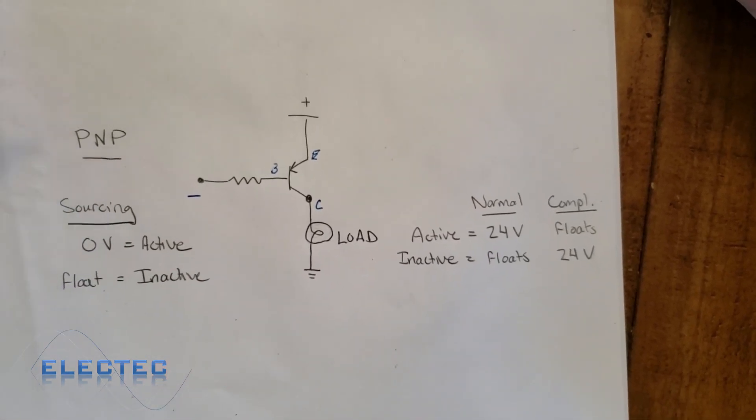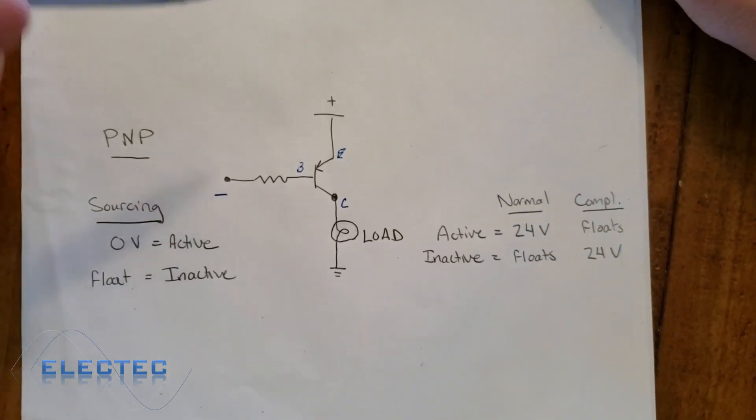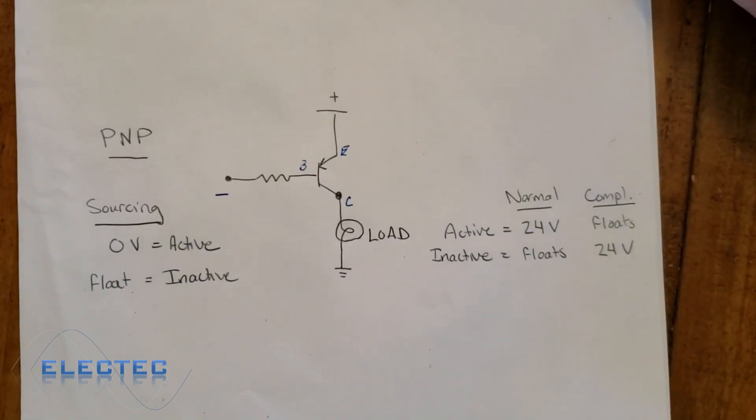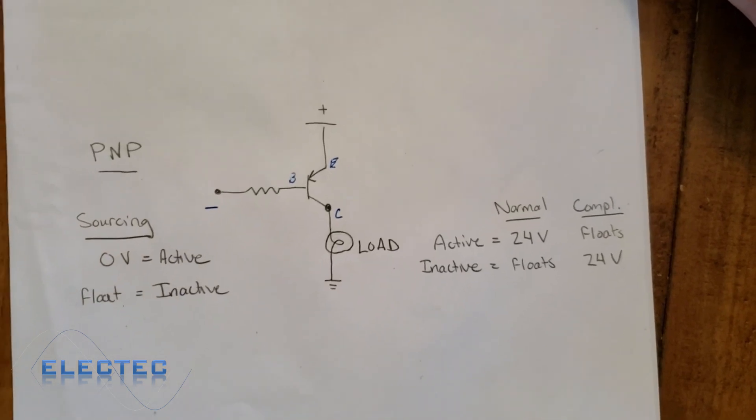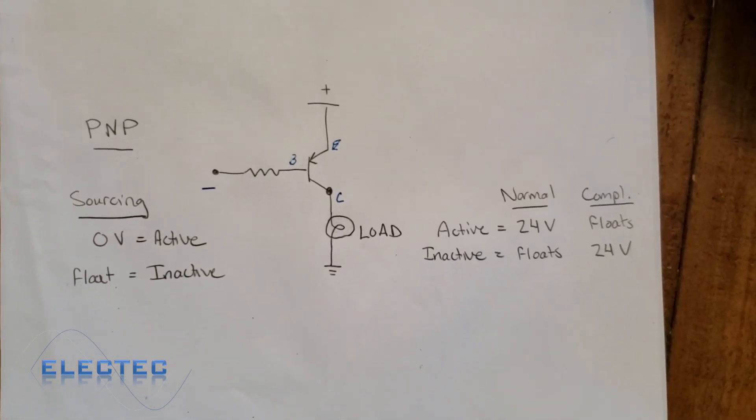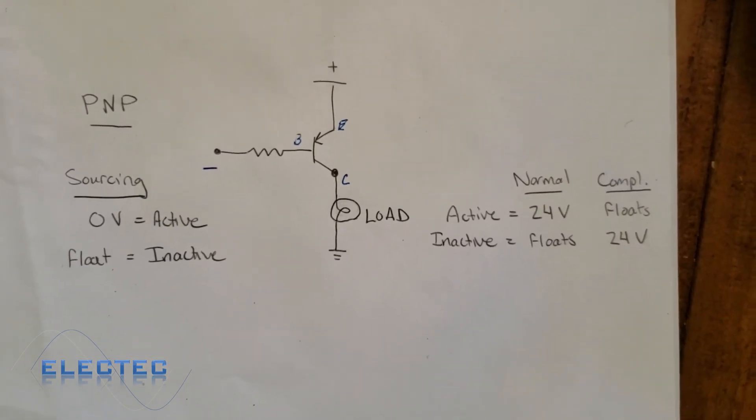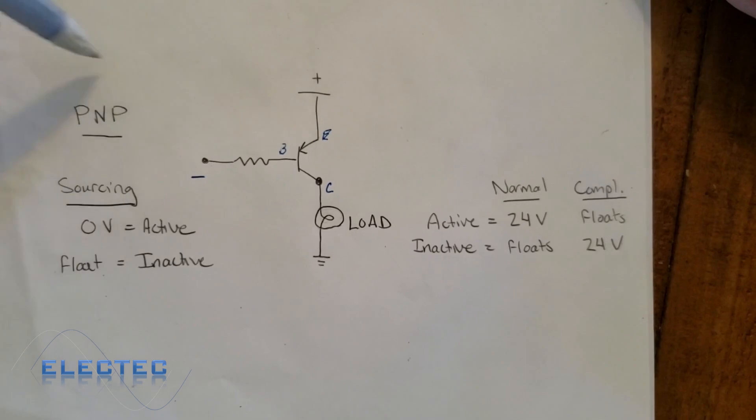If you need 24 volts, which is more common for the US standard, you would use PNP sensors. PNP sensors work directly with NPN inputs. So if you have a PLC that has inputs, or sinking inputs, they call it, that means you need a sourcing sensor to activate it. A sourcing sensor would be a PNP sensor.